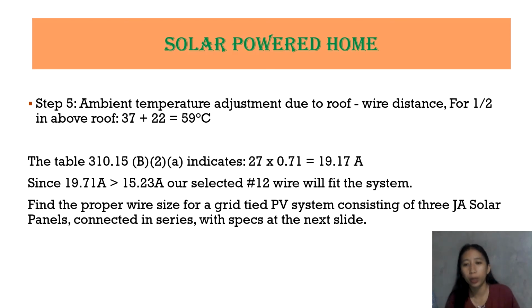Okay, so moving forward to step 5, which is the ambient temperature adjustment due to roof, wire distance for one half in above roof, 37 plus 22 is equal to 59 degrees Celsius. So, the table 310.15 B2A indicates that 27 times 0.71 is equal to 19.17 ampere. So, since 19.71 ampere is greater than 15.23 ampere, our selected number 12 wire will fit this system. Okay, so ang hinahanap nga natin is what could be the proper wire size para sa ating grid-tied PV system consisting of 3 JA Solar panels.